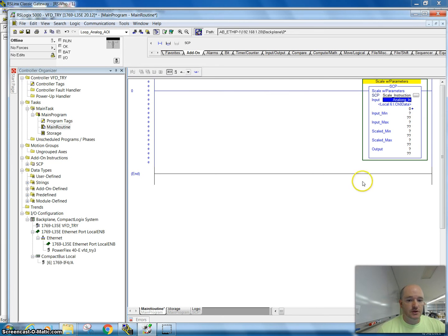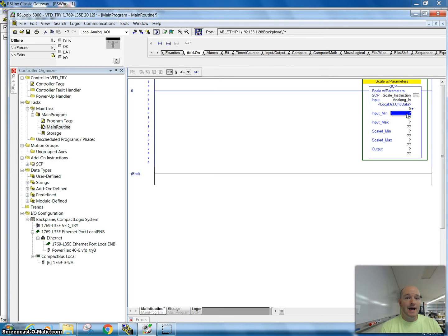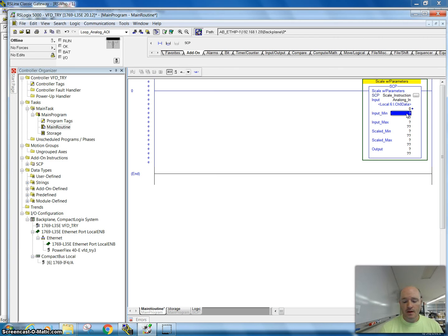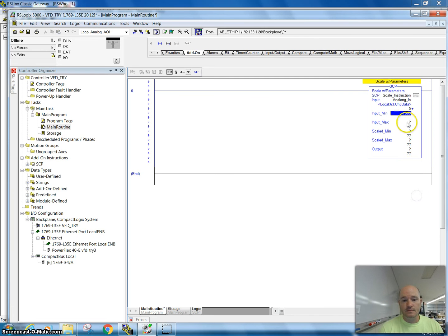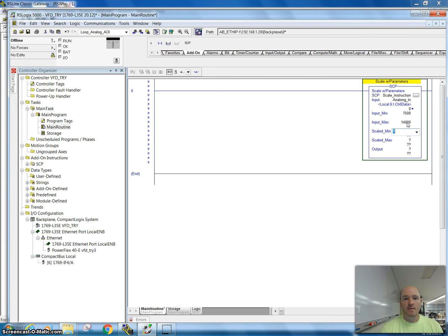Now for this instruction, we need to say what are my minimums and what are my maximums. This depends on how you're setting up your analog and what type of analog signal it is. We're just using a very simple 4 to 20 milliamp generator — not an analog proximity sensor, ultrasonic sensor, or weight sensor. I'm going to create a couple of values here between 7,500 and 14,000. These are going to be our minimum and maximum scales.